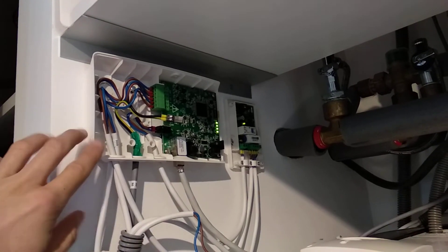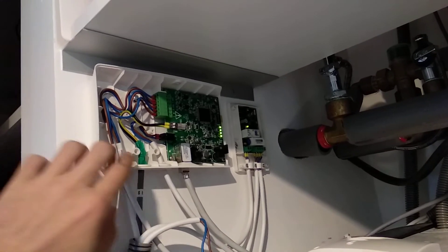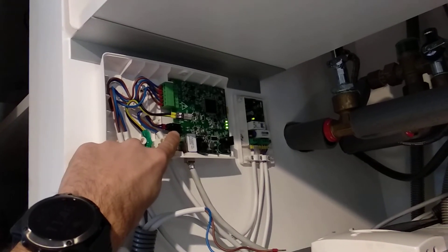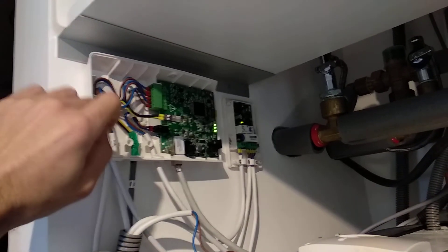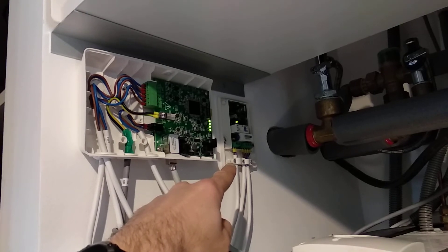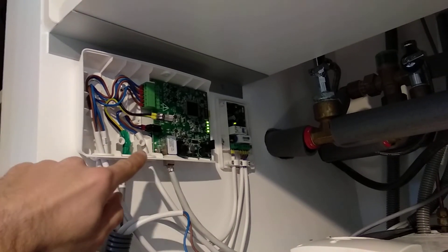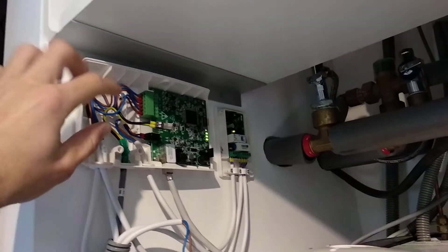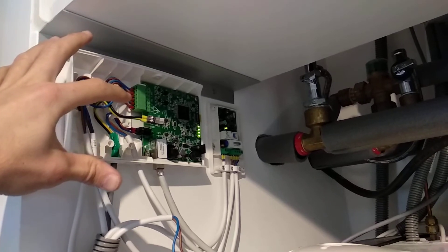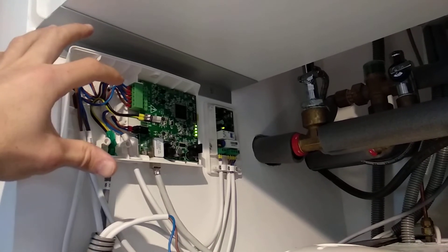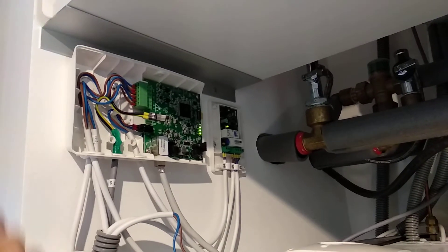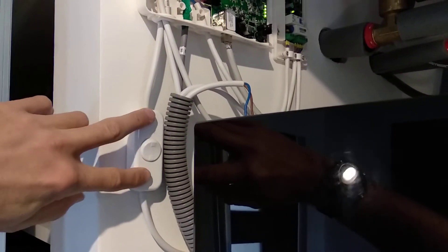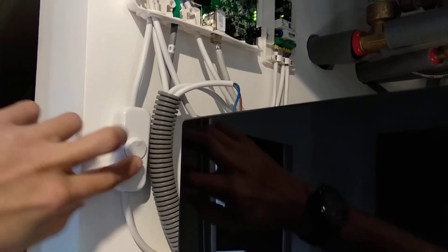This unit is connected to the Daikin Altherma 3 through P1 and P2, and this Zigbee dry switch is connected to the LAN adapter from Daikin. It provides an SG0 and SG1 signal. SG0 signal is actually the one you want; SG1 is just for my test purposes. I have added a manual switch to disable it completely or to enable it.